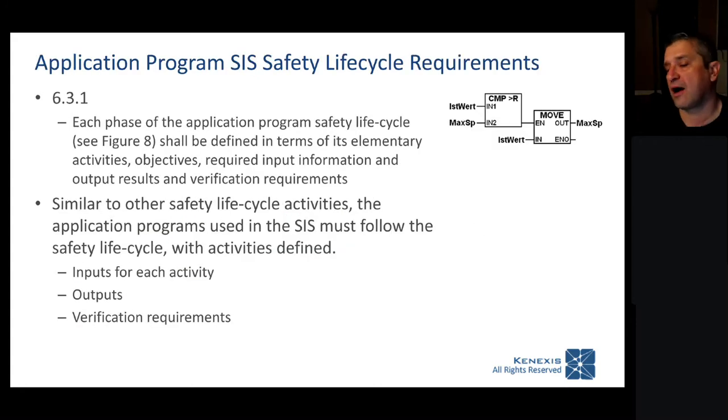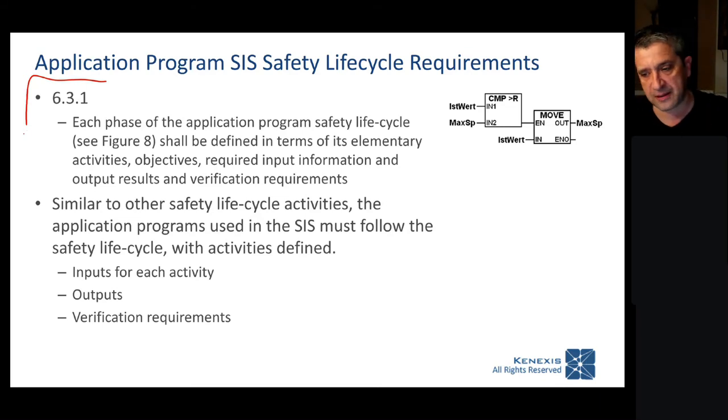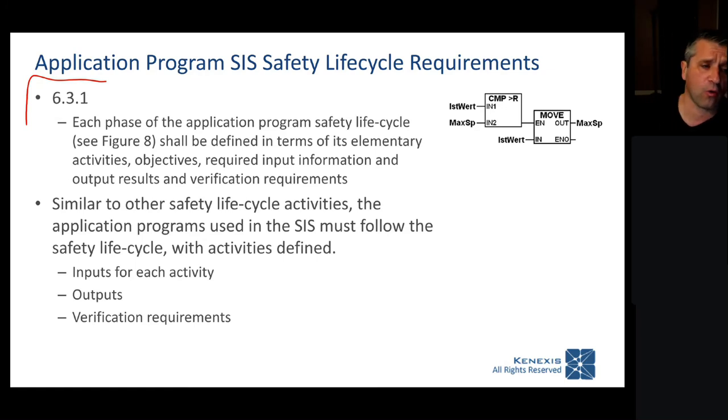And of course, I would say that the IEC 61511 standard pays a little bit too much attention to programming. Programming is a very big deal if you're writing in C# or Pascal or Visual Basic, high variability languages. But if you're using limited variability languages, which you should be if you're following the IEC 61511 standard, things like function block diagrams or ladder logic, it's a little bit more difficult to get yourself into trouble.